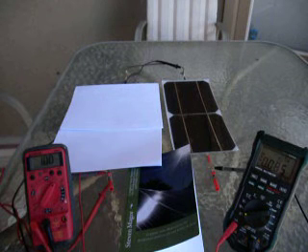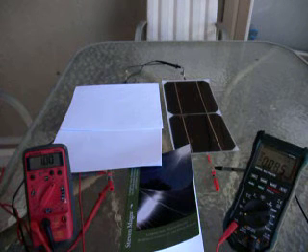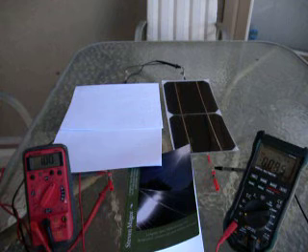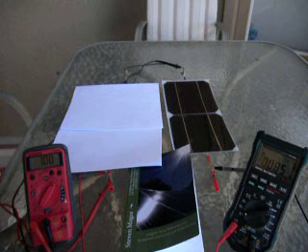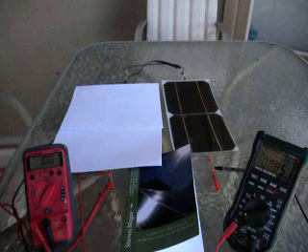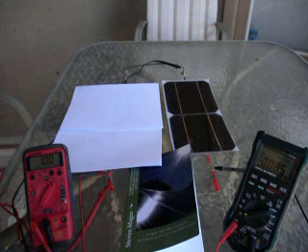This effect can actually blow your string fuses if you have multiple parallel strings connected together and one string is not performing very well because it is shaded or tilted in a different direction. You may find that you're quite frequently blowing string fuses, and this is an effect to look for.